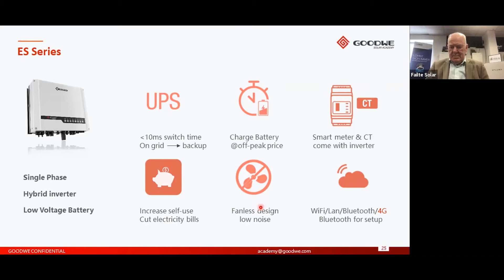you can actually charge them from the grid. Across the range, all our energy storage products come with these ancillary items, which are a smart meter and CTs. The smart meter is actually a separate ancillary device installed when you do the commissioning. It basically picks up the excess energy flow within the property and directs it to the battery for charging and discharging. Energy storage is all about using everything you generate and saving as much as you can for when you need it.